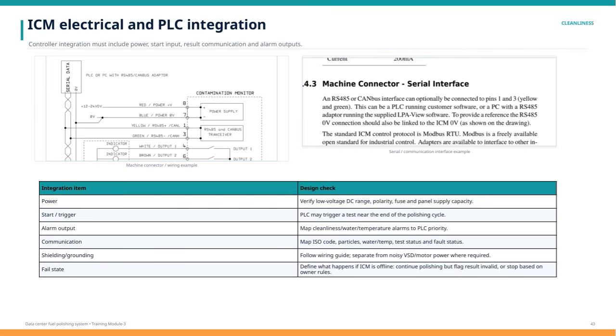Communication integration involves mapping ISO codes, particle counts, water and temperature data, test status, and fault status to ensure comprehensive monitoring. Proper shielding and grounding are crucial to reduce electrical noise. Following the wiring guide, it's important to separate signal wiring from noisy sources like variable speed drives or motor power cables. Finally, defining the fail-safe state is essential. If the ICM goes offline, the system must be configured to either continue polishing while marking the result as invalid or to stop the process entirely, depending on the owner's operational rules. This ensures safety and reliability within the fuel polishing system.